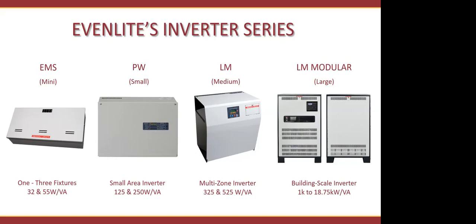We've also accounted for overload. We're talking about 110% overload on these inverters as well for up to 10 minutes. So as far as inrush goes, overload, you're definitely covered.